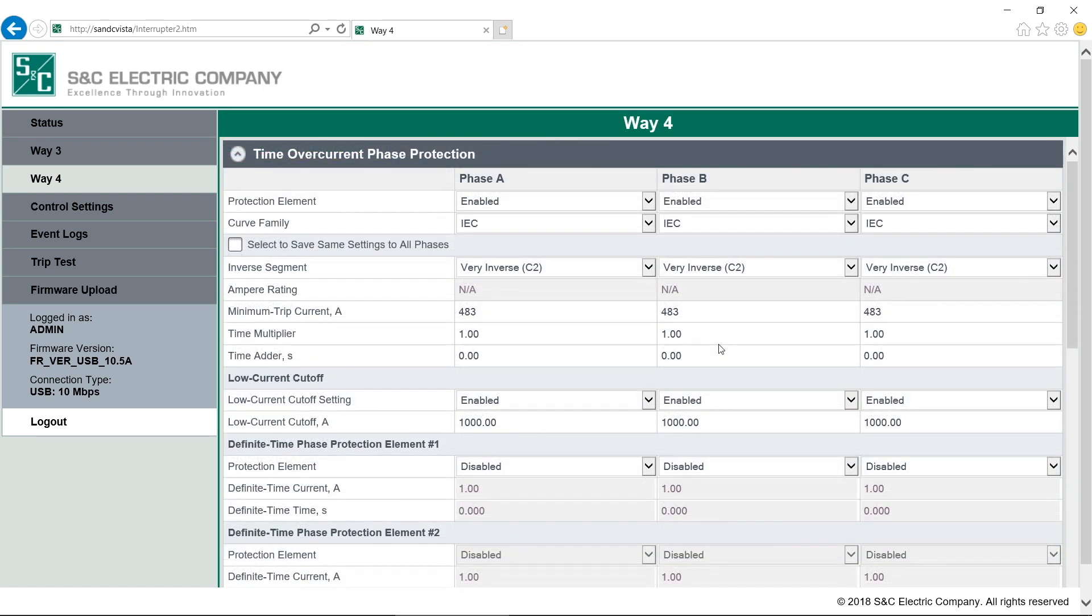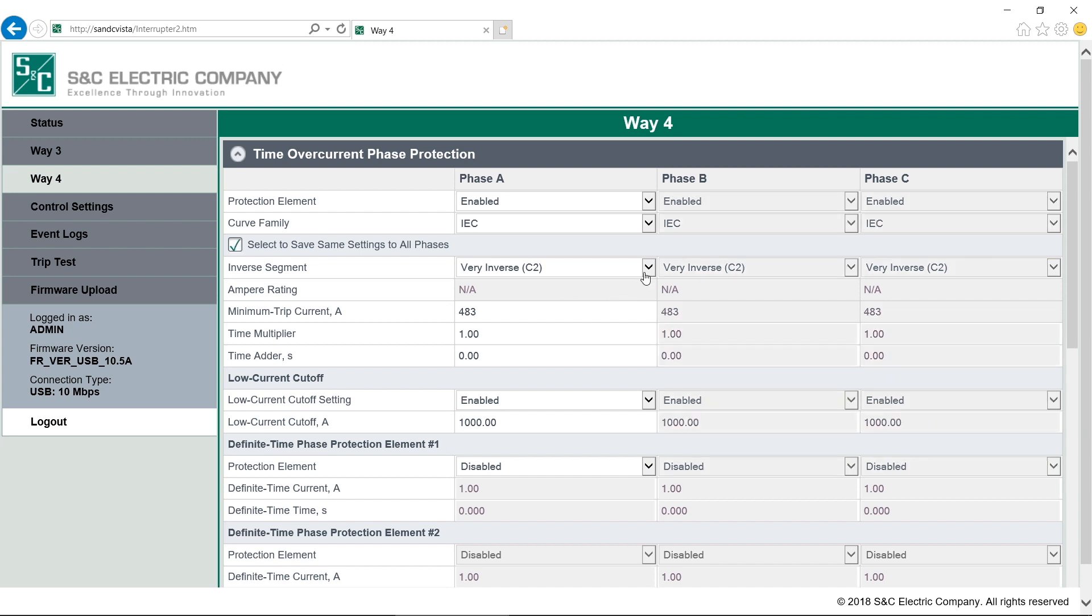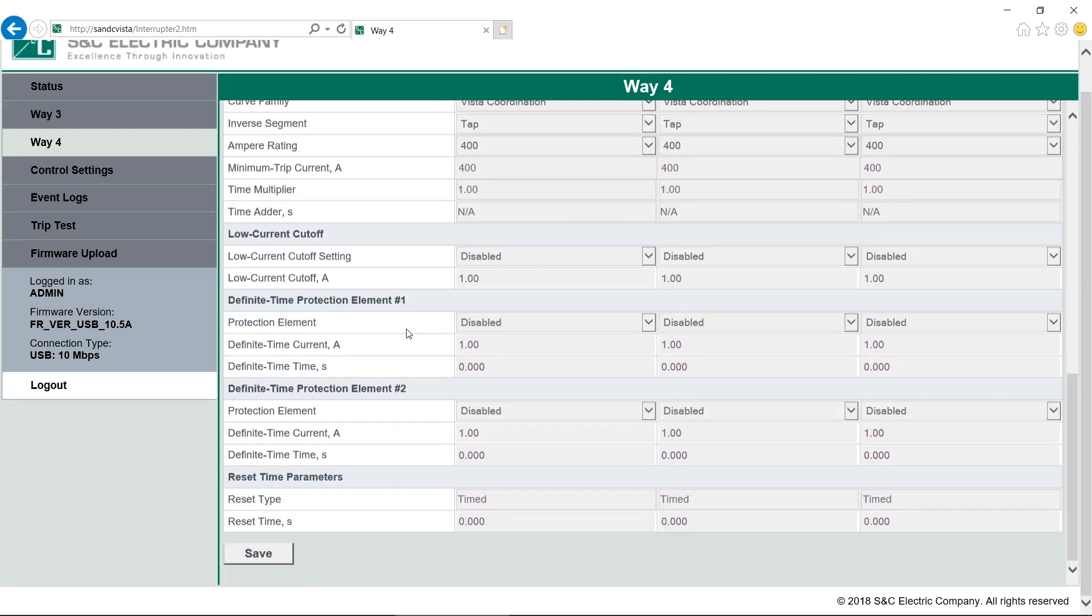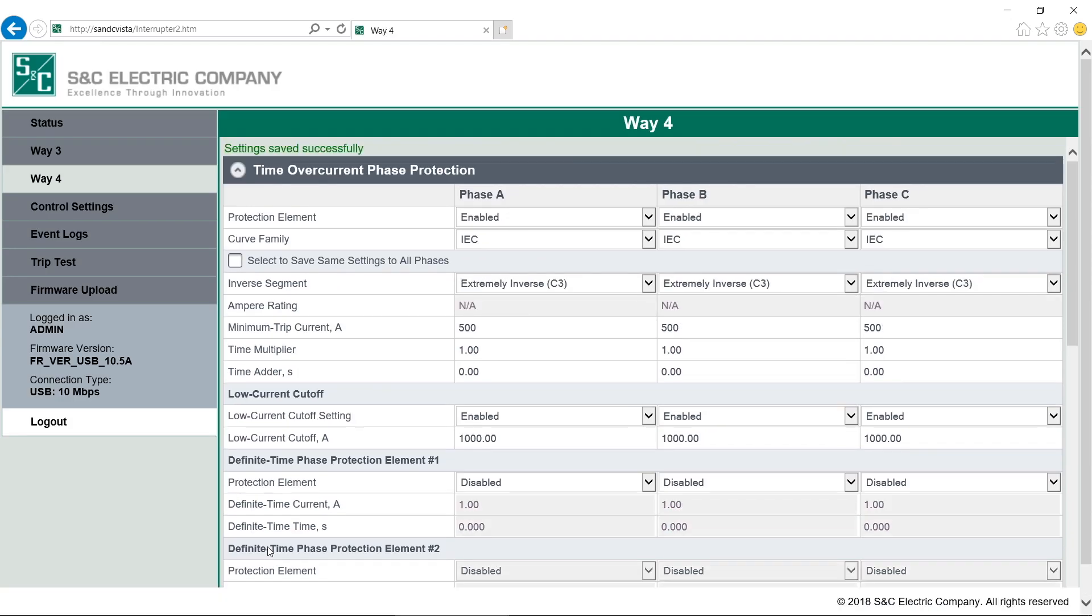Let's look at a single-phase fault interrupter. Way 4 is set for single-pole tripping and single-pole lockout. Each phase can be programmed with separate protective settings. We can see phases A, B and C are all enabled. None are grayed out. Settings are chosen the same way as three-phase fault interrupters. If we want to use the same settings for all three phases, we can select the checkbox Select to Save Same Settings to All Phases. It will gray out phases B and C. Then we can make changes in phase A. Once we save, phases B and C update so all three phases have the same settings. However, settings for Ground, Negative Sequence, or Sensitive Earth Settings are not available with this trip mode.